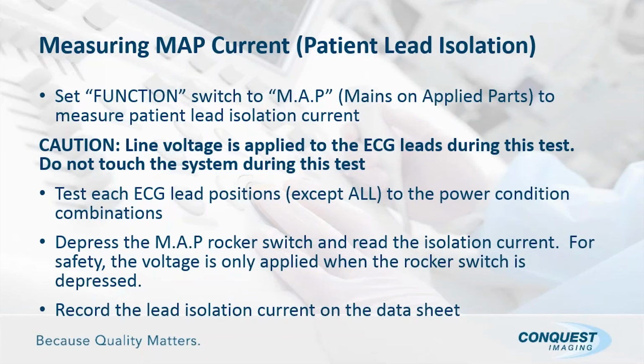Set the function switch. Now we're talking another condition, MAP, patient lead isolation. This condition measures the patient lead isolation current. And this is kind of unsafe, so you have to be careful when doing this particular MAP, mains on applied parts test, because you're actually taking line voltage and applying it to the ECG leads during the test. So you don't want to touch the system or the leads in this condition, because when you go into the MAP on the rocker switch, you're applying that voltage, and if you're grounded and touching the lead, you're going to get the line voltage.